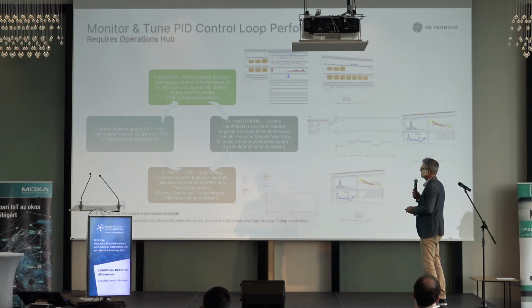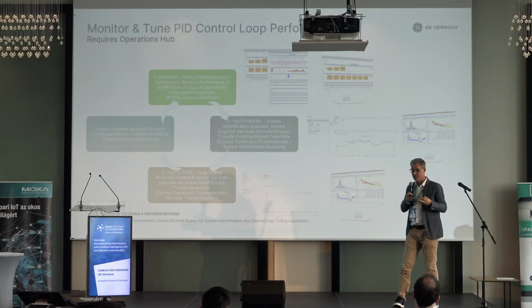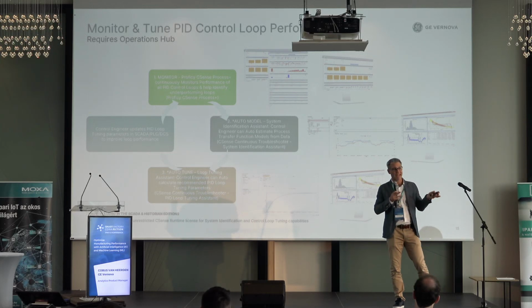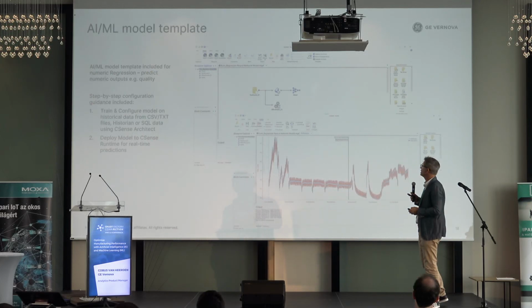Now, with this runtime, CSense out of the box allows you to monitor and tune all your PID loops. With the free runtime, you are allowed to monitor 1 loop, just to get to know it, do a POC, get to see how it works. If you upgrade to full CSense and you buy a CSense runtime, you can also do tuning of the loops and monitor all your PID loops.